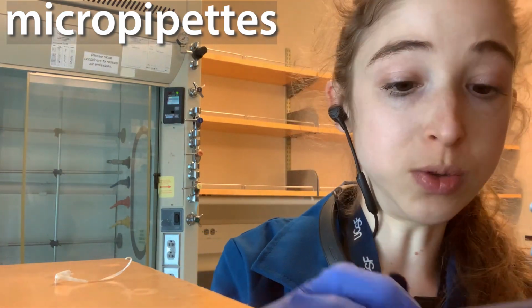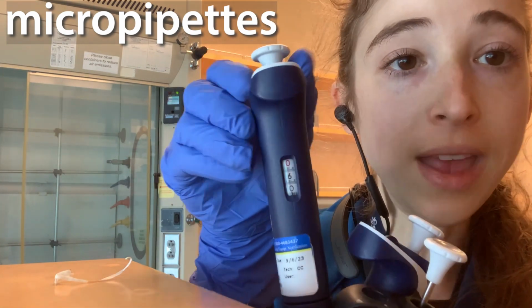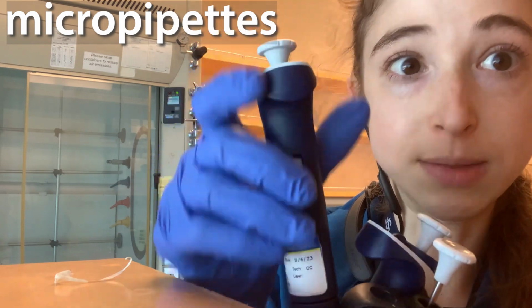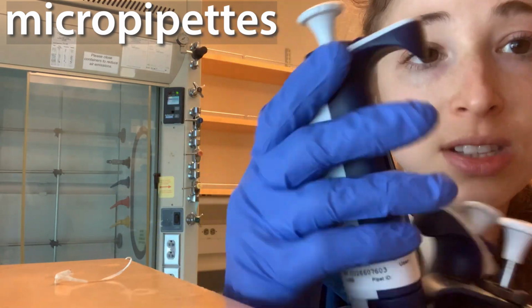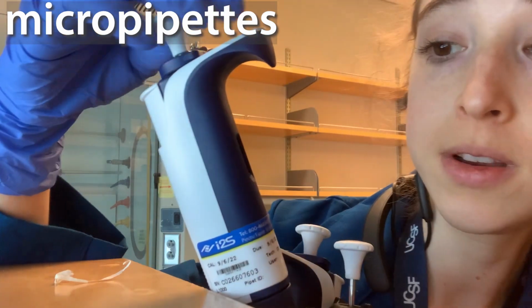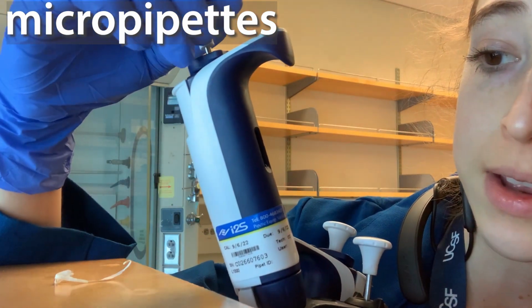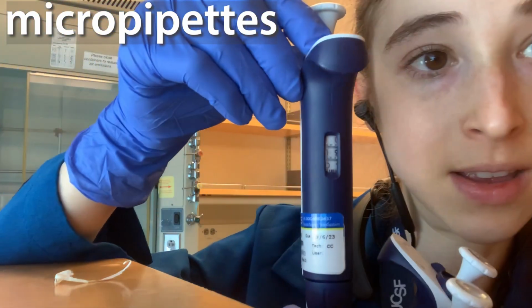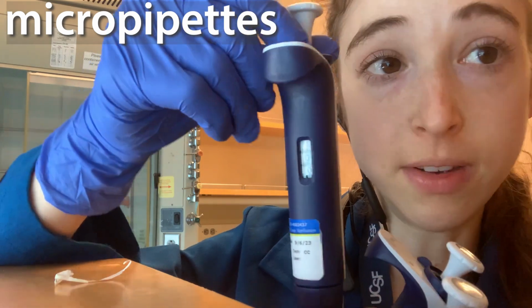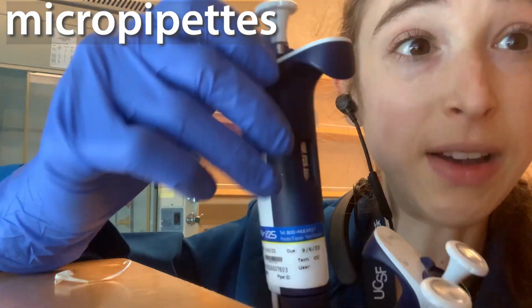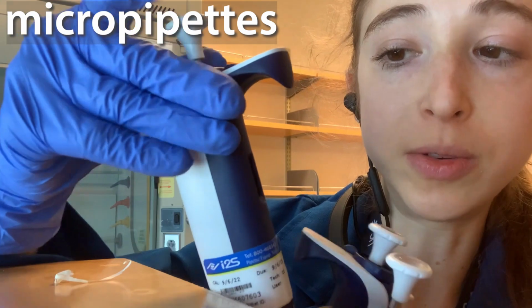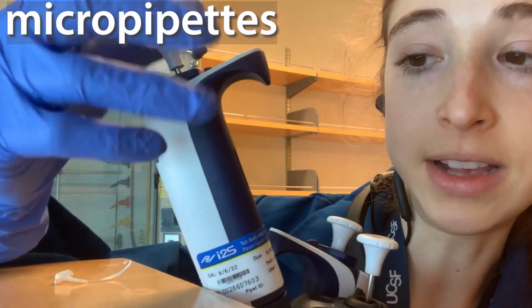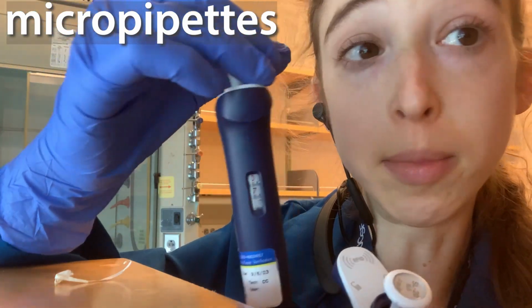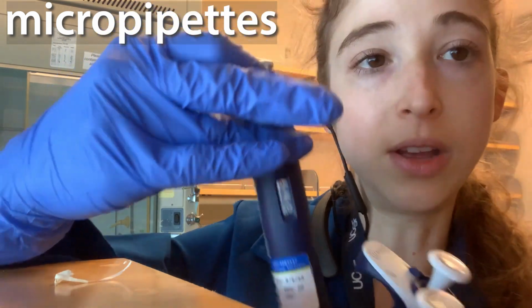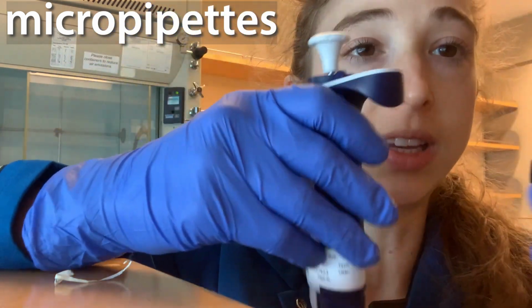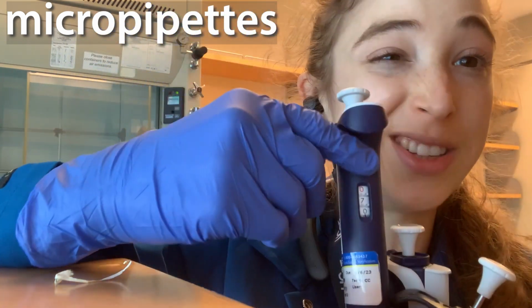And if I were to go to a P1000, well, now I can't go anywhere after the decimal point unless I'm below 1,000. So you can see if I go to 1, then the 1 is before, and then you have 2 after, but you can't go above, so all you can do is go below. You're always going to be working below that decimal point, because that would be in terms of milliliters.